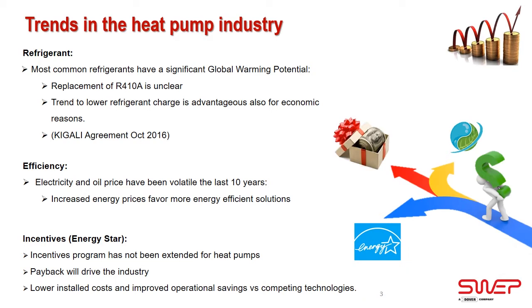Trends in the heat pump industry. The most commonly used refrigerant in heat pumps is 410A. It does have a high global warming potential, so there are a lot of refrigerants that want to take its place, but there is no clear roadmap how and when this can happen. So we see that 410A will remain with us. However, there is a strong trend to lower the refrigerant charge in systems, reaching a higher BTU per pound of refrigerant, and the reasons are also economic, as you can save money on refrigerant doing so.